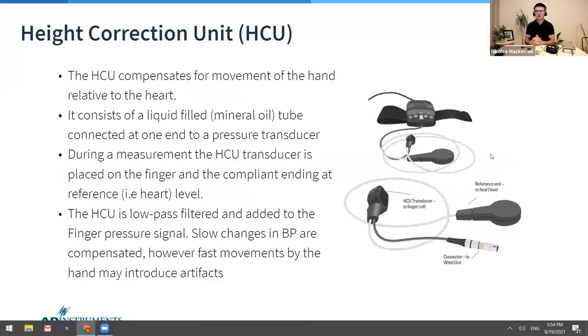So the height correction unit is a really important aspect of this tool. Primarily, we're interested in mean arterial pressure here. As we know, if we move our hands above our head, then the pressure within our hands is going to fall naturally. That does not necessarily mean it is going to be an accurate representation of our mean arterial pressure at that time. So what the height correction unit does is essentially compensate for that type of movement.